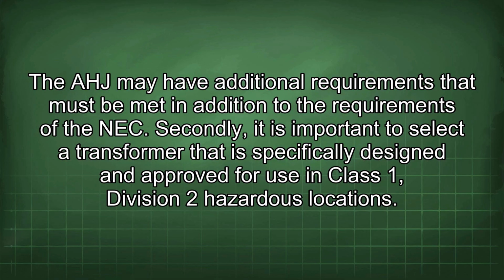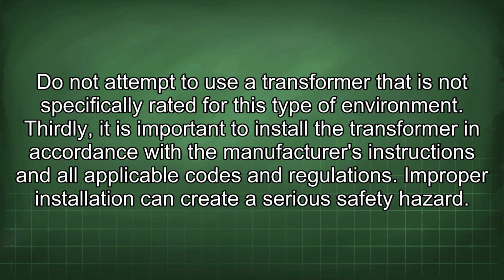Secondly, it is important to select a transformer that is specifically designed and approved for use in Class 1, Division 2 hazardous locations. Do not attempt to use a transformer that is not specifically rated for this type of environment. Thirdly, it is important to install the transformer in accordance with the manufacturer's instructions and all applicable codes and regulations. Improper installation can create a serious safety hazard.